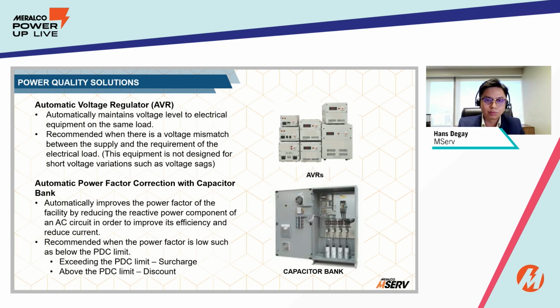When dealing with voltage mismatch present in the facility, AVR can help maintain the voltage levels to the appropriate level of the equipment. It should be noted that this is not designed for voltage sags. Step-down transformers can also be used but AVR is better in regulating to a desired voltage level as long as it meets the range of the specification. Although step-up or step-down transformers can also be used, thorough study must be done because voltage levels do fluctuate.